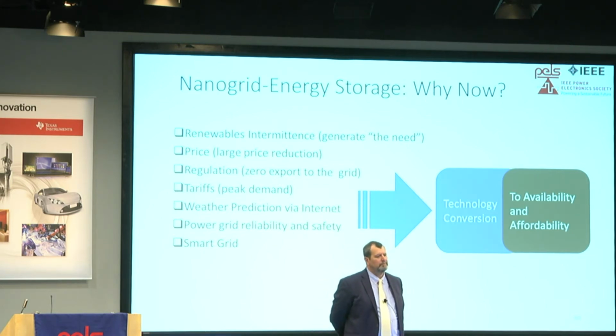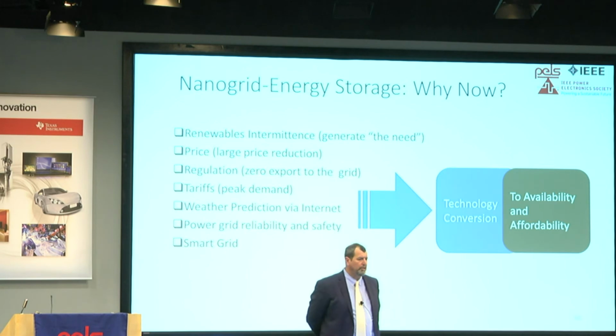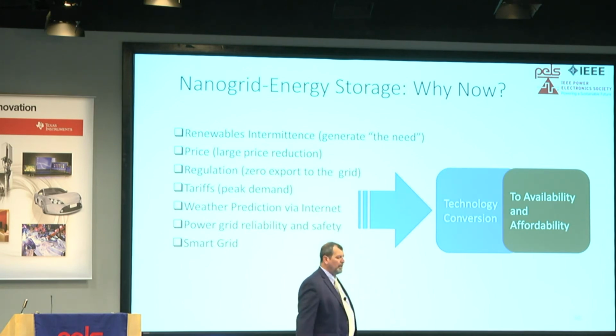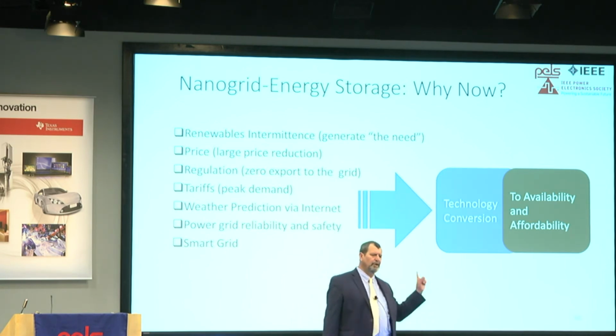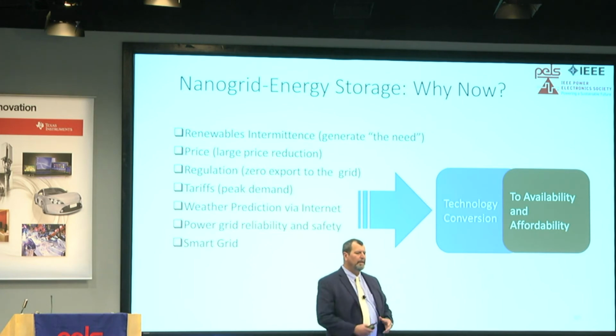I had a question about transformer-less inverters - are they more expensive? No, they are way cheaper. The problem is you have to pass a certification, I don't remember the number, that says you cannot have ground current more than a certain specification.